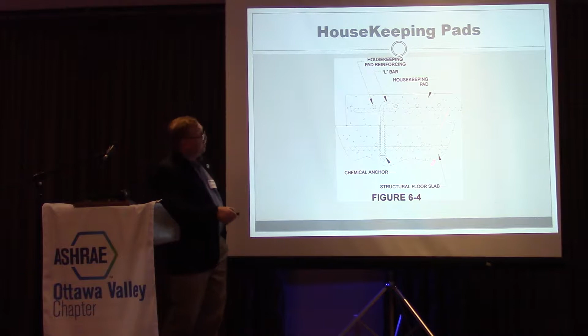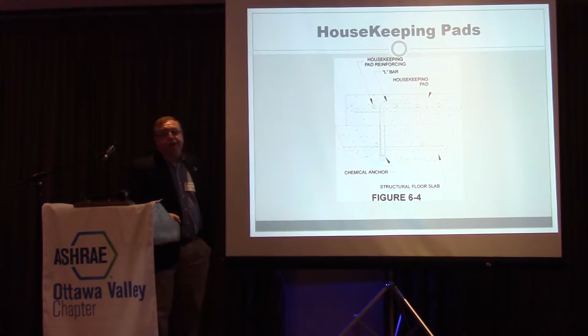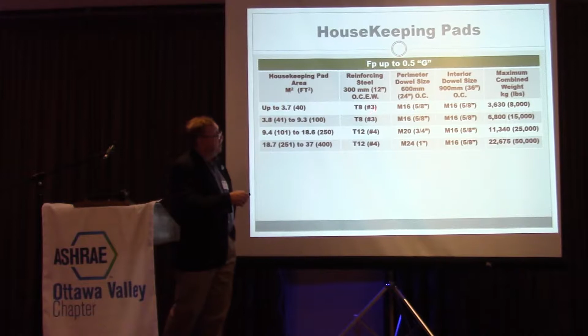This is typically what it looks like: reinforcing and some kind of dowel down into the structural slab. At ASHRAE, we've put together a set of charts for different seismic zones. So if you have a piece of equipment and the housekeeping pad with a combined weight of X, up to a given number of square meters, this is all you need: number 3 rebar with perimeter doweling at 5/8 inch, and interior doweling.